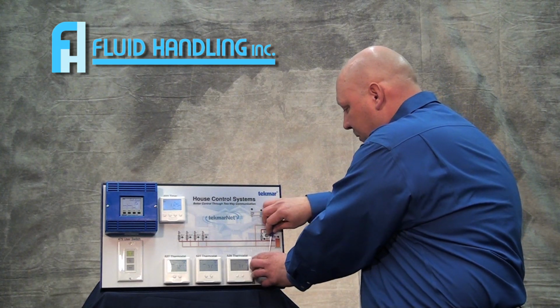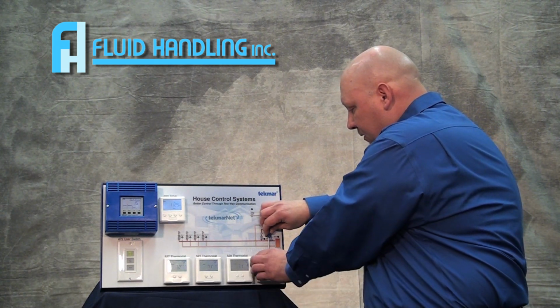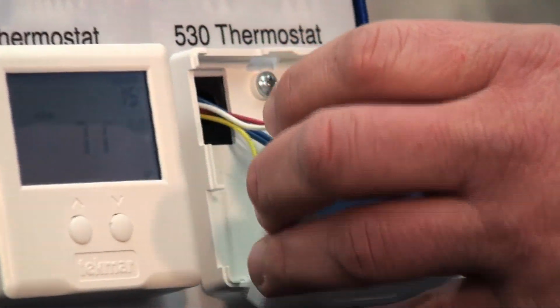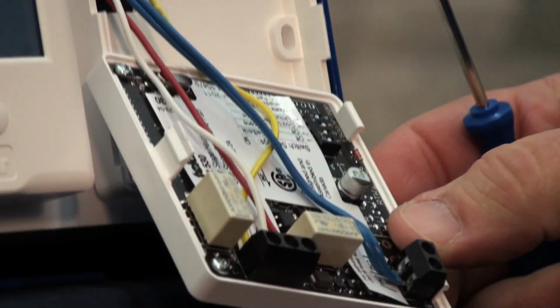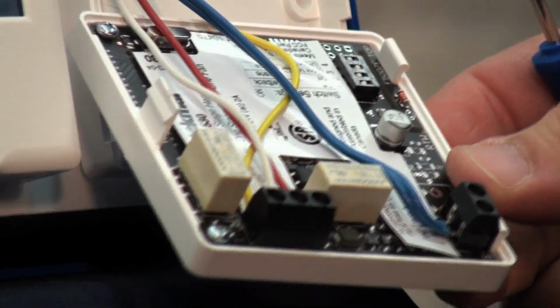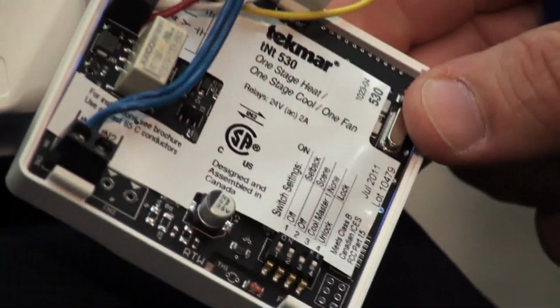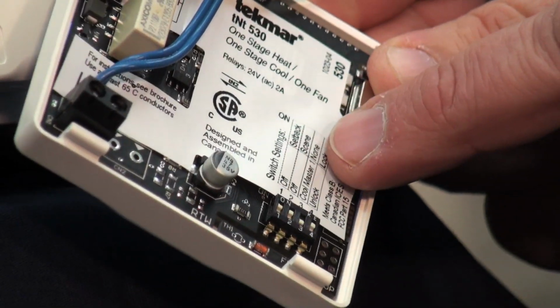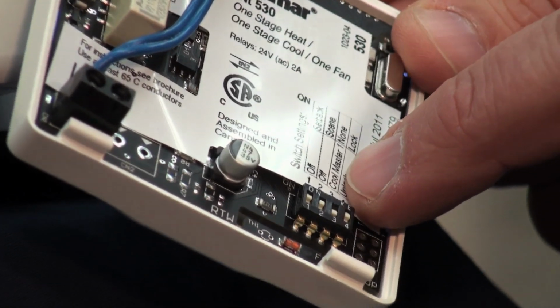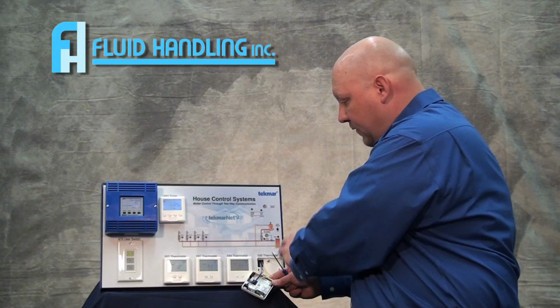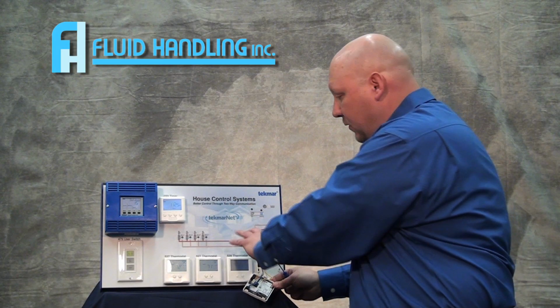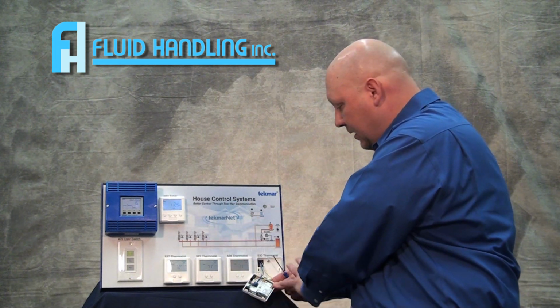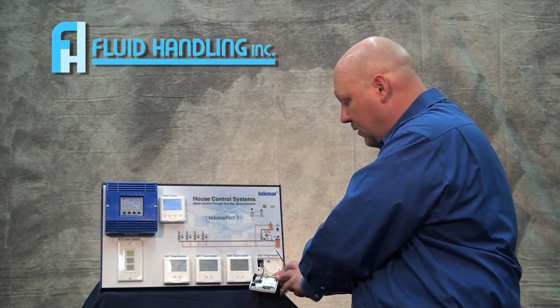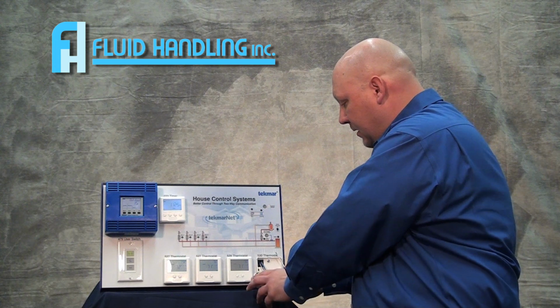The 530 thermostat is our heating and cooling stat. So the same applies for removing it, but you can see we've got a few more options on the back of the stat. You do have your same 4 dip switch settings. You're going to have your setback, your scene, and now you can tell it if it's the cooling master or if it's a standalone by itself with no zones associated with it. You can leave that to none, or you can lock or unlock it.